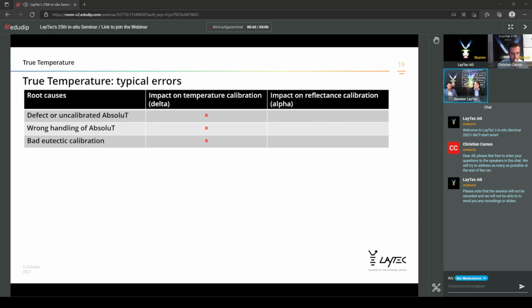Some users still like to use eutectic wafers for calibration, and they definitely have established and qualified a reliable and repeatable procedure to do that. Although we sometimes see and get reports that apparently the evaluation of the state-changing spot of the eutectic wafer has either not been met correctly, or maybe the thermal process to reach that specific temperature hasn't been maintained well enough or has been too quick, so that the users missed the spot and then derived a wrong temperature spot to calibrate for the delta calibration.